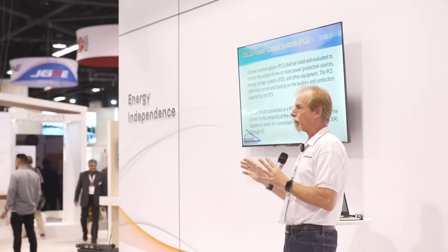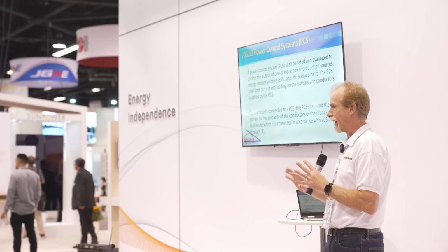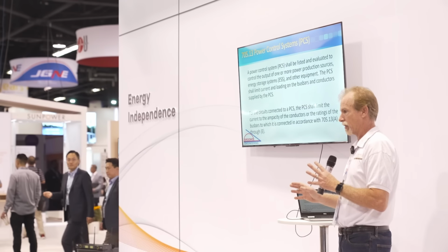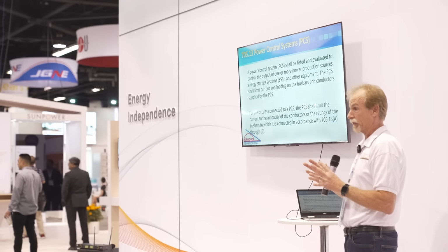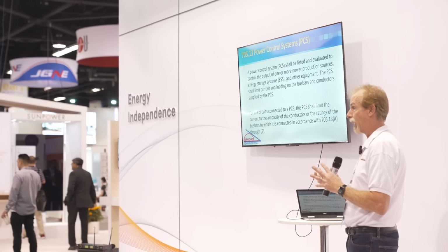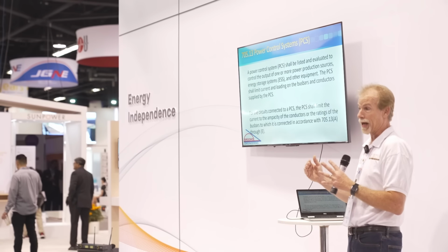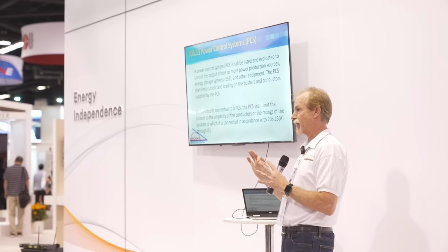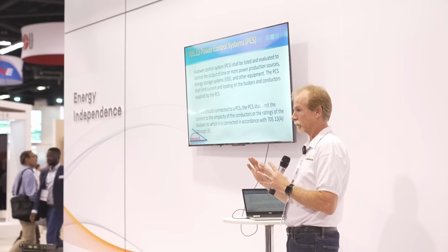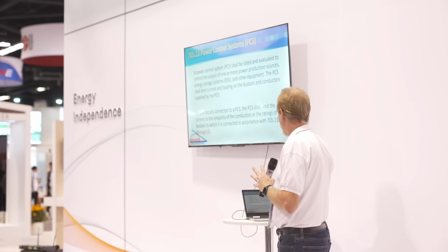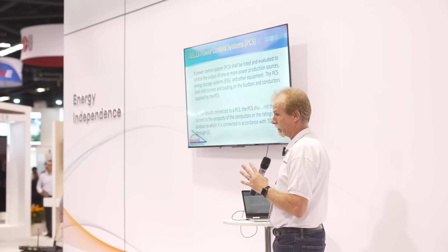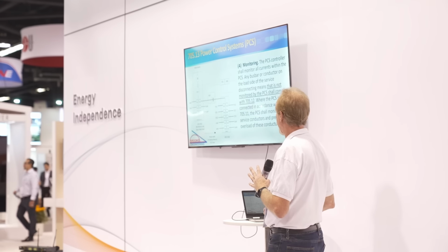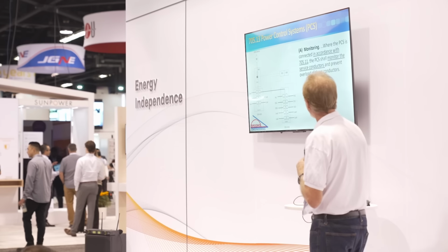Now, it probably would not work very well if I put that big of a PV system on a 100 amp service, because I'd be really challenged to find the loads to suck up that extra power. I'd be in curtailment mode a lot. But technically it's fine, and safety-wise it's fine. So the code would not allow you to do this before, and it does now. There you go.